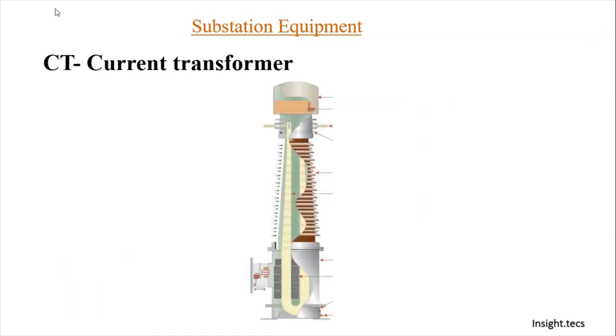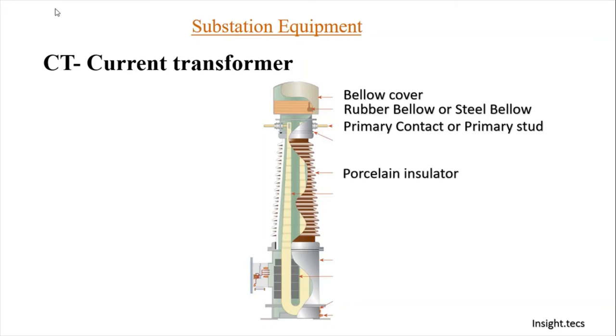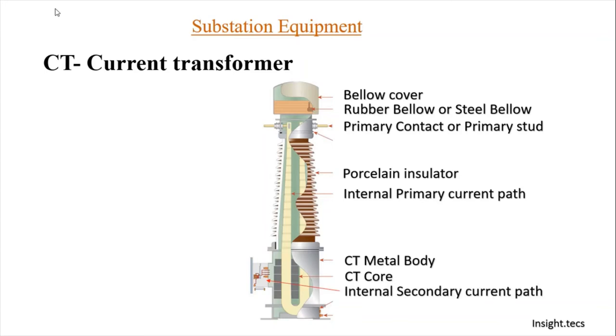The construction of CT. We will consider a dead tank oil filled CT because that is widely used in substations these days. The first component is a bellow cover. Below that is a rubber bellow or steel bellow. This is the indication of some kind of dissolved gases present inside the CT, because whenever there is any fault and the arc is quenched inside within the oil, then the rubber bellow gives the indication that there might be some dissolved gases present inside the CT. Next is a primary contact or primary stud, then a porcelain insulator, internal primary path that can be called as the primary winding, then there is a CT outside metal body, then there is a CT core and internal secondary current path or secondary winding, then there is a tan delta point using which we can conduct a tan delta test on the CT.